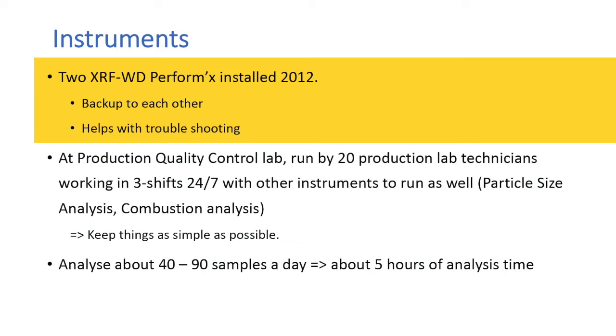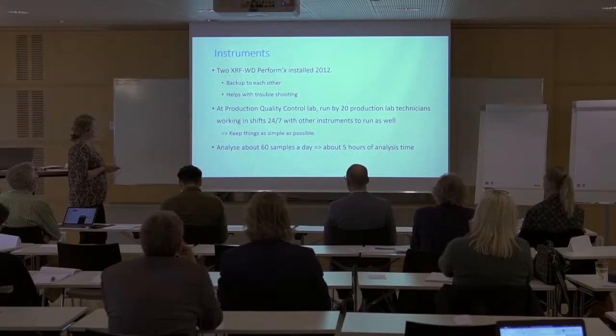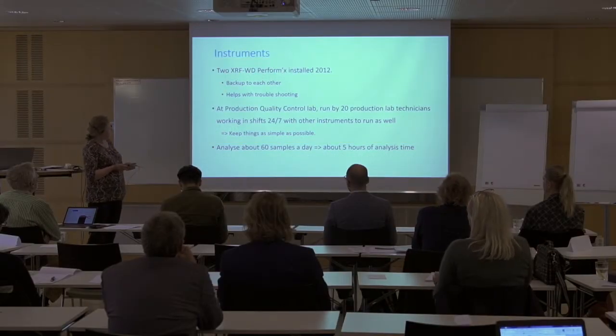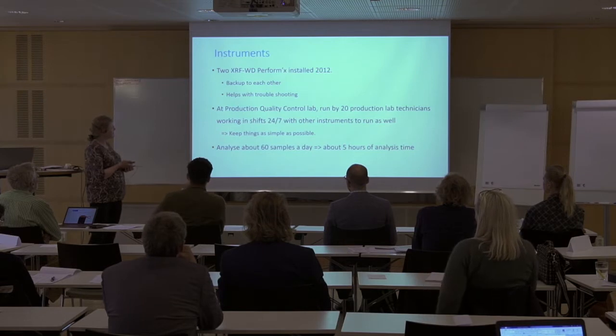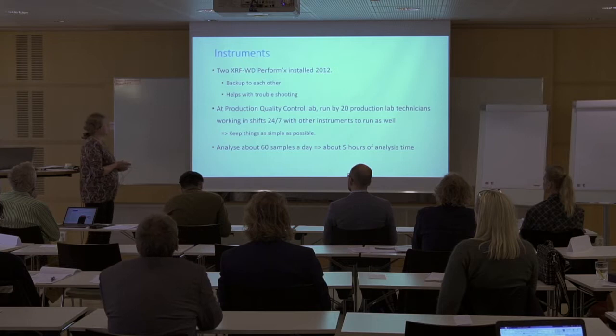Two XRF wavelength dispersive Perform'x installed 2012. There's a big benefit to have two. They are a backup to each other, and it also helps with troubleshooting if a sample says one thing on one and something else on the other one. We can know if it's the samples or the instruments that are messing up things.